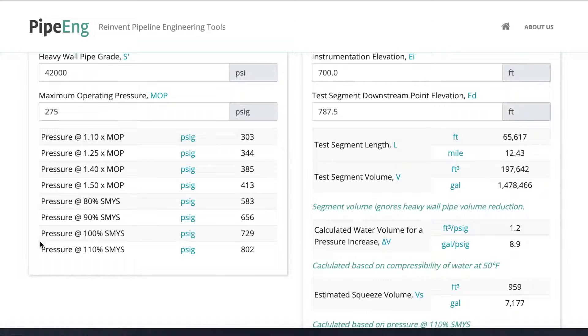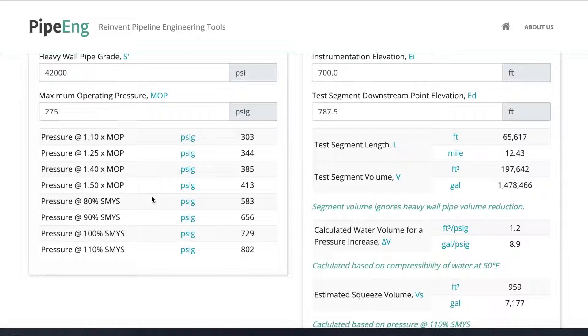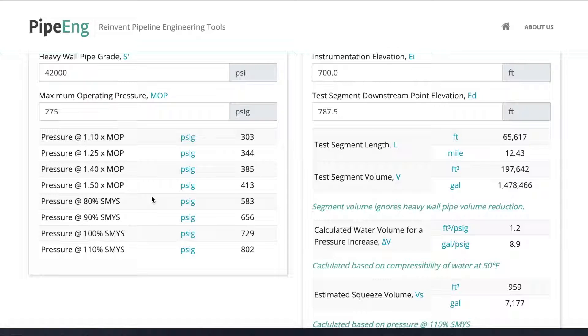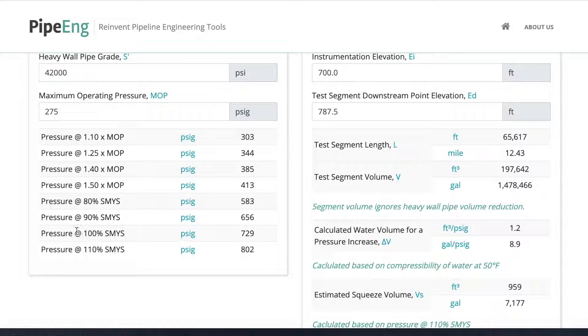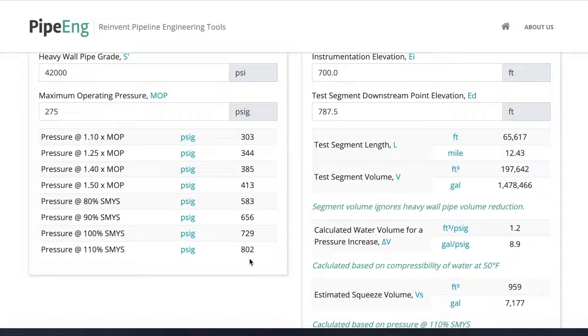The next set of pressures are pressures at a different percentage of SMYS. Usually, the upper limit of your test segment, also saying maximum test pressure, is determined by the percentage of SMYS. A lot of times, we can assume 110 percent SMYS is the upper limit, or sometimes you want to be a little bit more conservative, you assume 100 percent SMYS. Then the pressure showing here can be a great reference for you to check your test pressure to make sure they're within the limit.